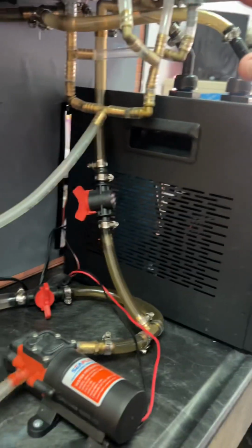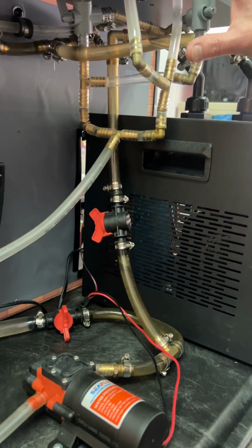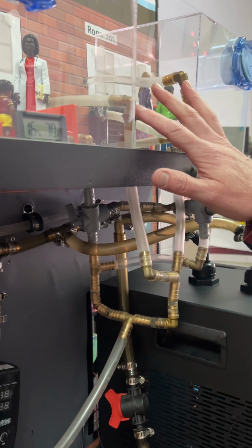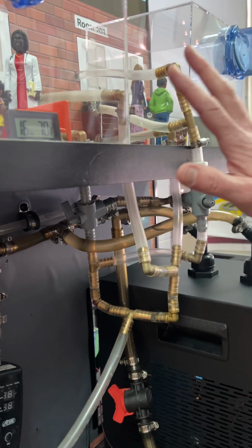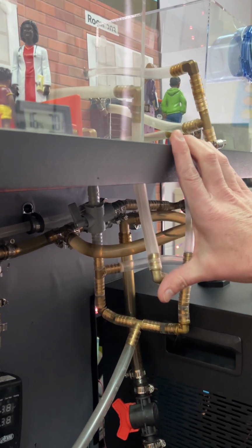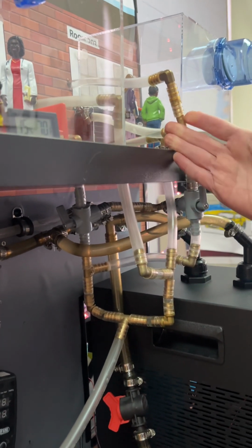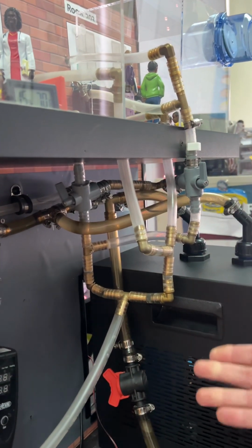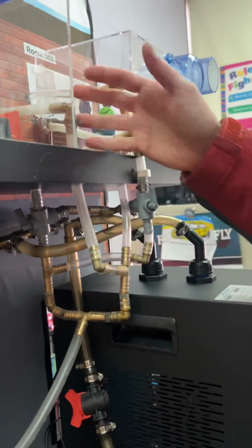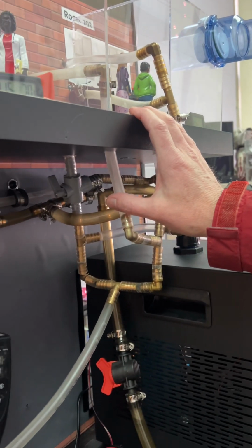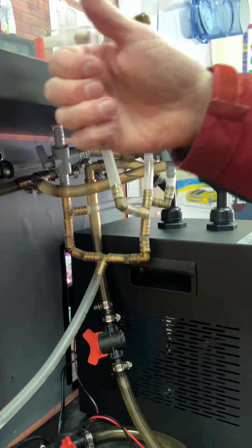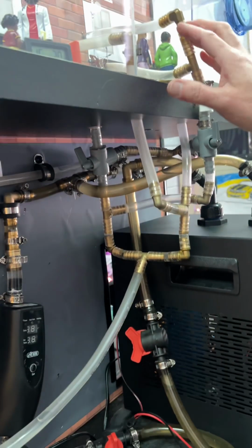One other point, that, as is typical, not in every building, but in a lot, the hot water and cold water share the same pipes. So we can either be cooling, air conditioning, as most people call it, or we can be in heating mode. But the building has to do one or the other. It's not going to do both simultaneously, because it's using the same pipes. Okay. So we call that a two-pipe system. One pipe sending the water out, one pipe bringing it back. So the name is two-pipe.